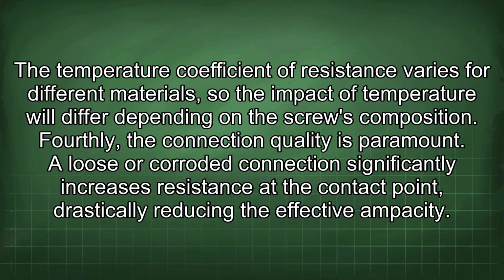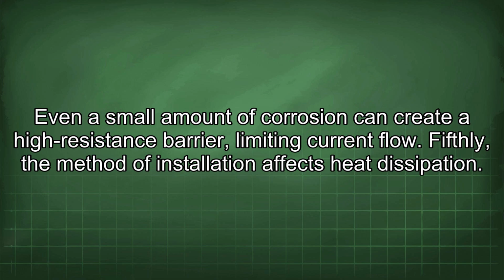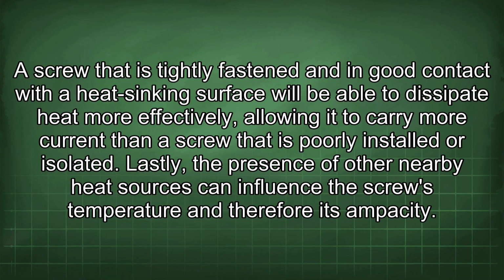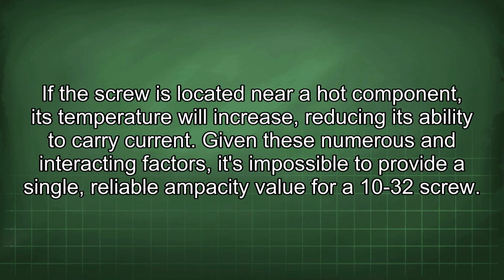Fourthly, the connection quality is paramount. A loose or corroded connection significantly increases resistance at the contact point, drastically reducing the effective ampacity. Even a small amount of corrosion can create a high resistance barrier, limiting current flow. Fifthly, the method of installation affects heat dissipation. A screw that is tightly fastened and in good contact with a heat-sinking surface will be able to dissipate heat more effectively, allowing it to carry more current than a screw that is poorly installed or isolated. Lastly, the presence of other nearby heat sources can influence the screw's temperature and therefore its ampacity. If the screw is located near a hot component, its temperature will increase, reducing its ability to carry current.